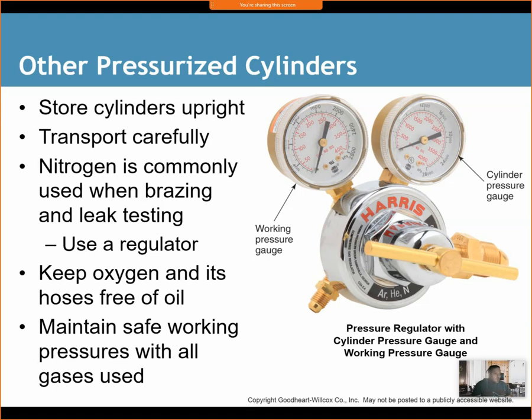Maintain safe working pressures with all gases used. So here we've got a picture of a regulator. This regulator tells you what the actual pressure is inside that cylinder. Generally it's going to be about 3,000 psi when fully charged, and as that pressure drops, you'll see the little needle move accordingly. This is our working pressure.